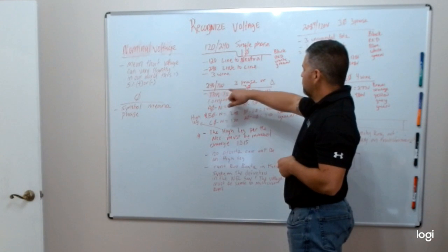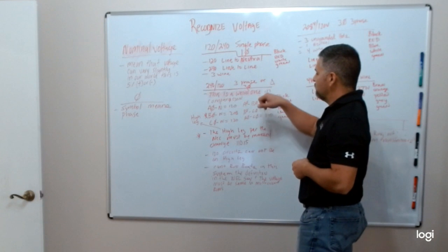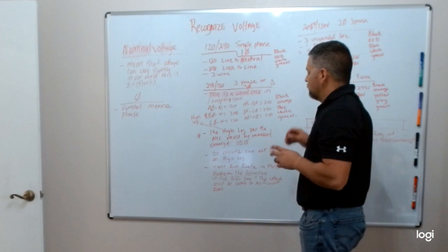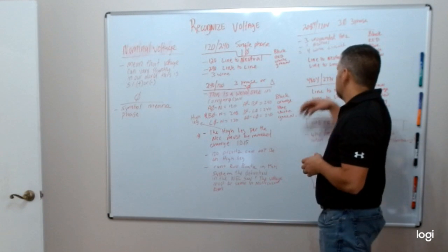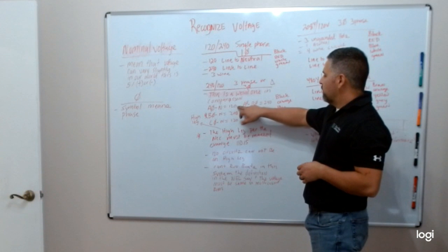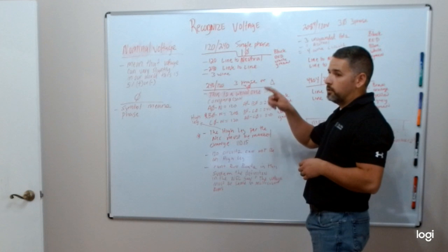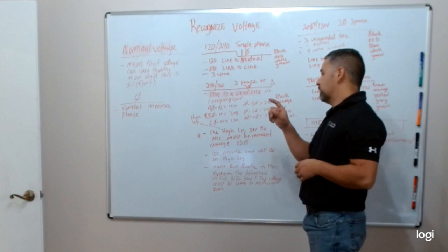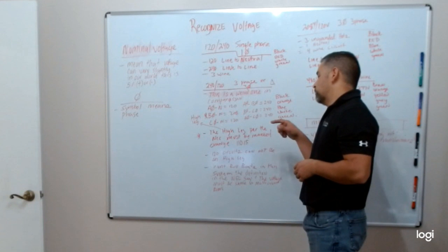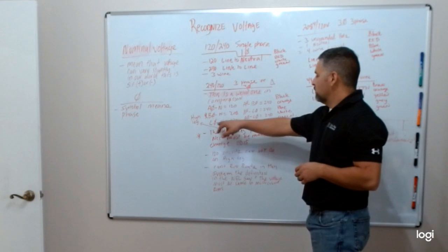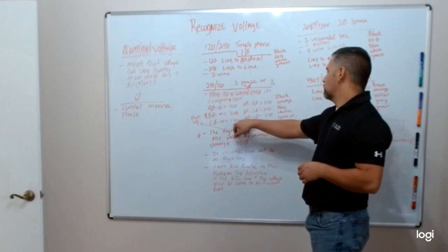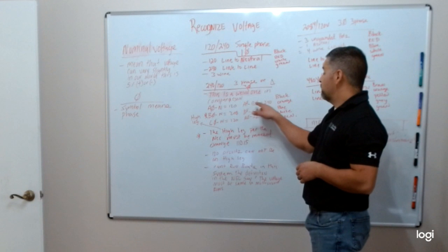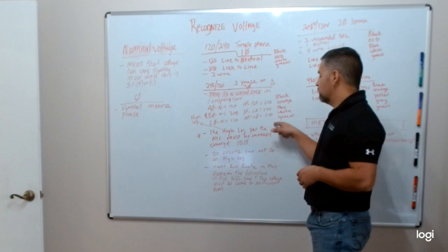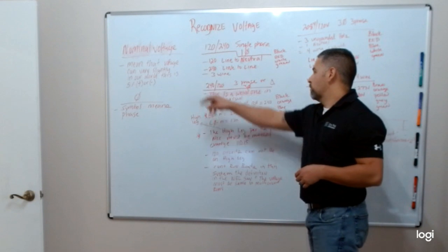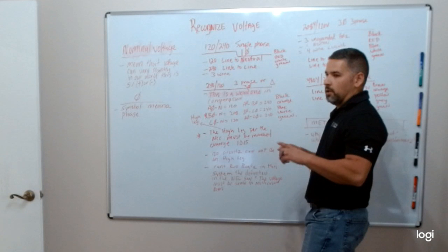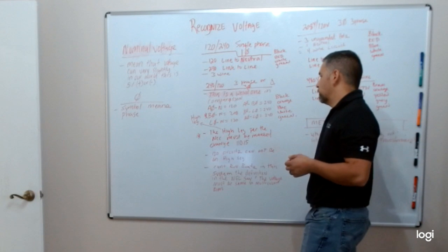So the next system is going to be the 240-120 three-phase. It's a delta system. This is kind of the weird one in comparison to the rest of them, because your A phase is going to be at 120 from line to neutral. Your B phase from line to neutral is going to be 208, which is weird. And then C to neutral is going to be 120 again. And then when you do phase to phase, you're going to have 240 on all the phases. And that's why it goes 240, 120, because it's on a delta system versus a Y system.